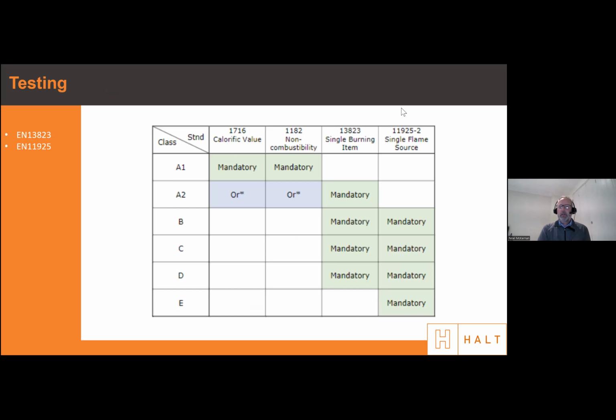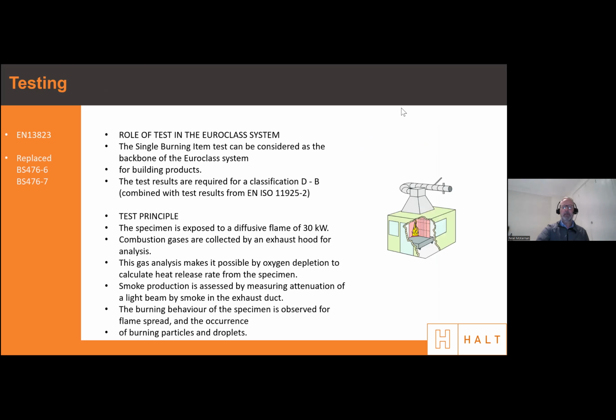So as I said, there are two elements for 13823, which is the standard for reaction to fire, 13501 standard. The two elements are the SBI test and the ignitability test. Both those elements are mandatory if you want to declare a product Euro Class B. The two tests are vastly different, but the SBI test has now become more or less the backbone of the Euro Class system.